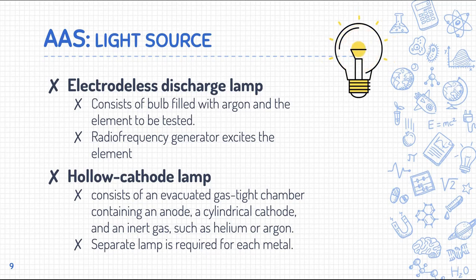The bumping of those ions into those metals will cause excitation. And when an atom is excited, as it returns back to its ground state, it releases light. That is how your hollow cathode lamp produces light. It first attracts the ions to the cathode, bumping into the metals, and then eventually those atoms are excited and return to their ground state, producing the light.